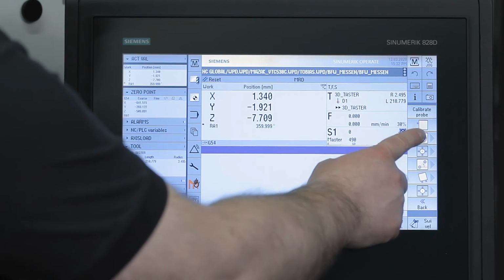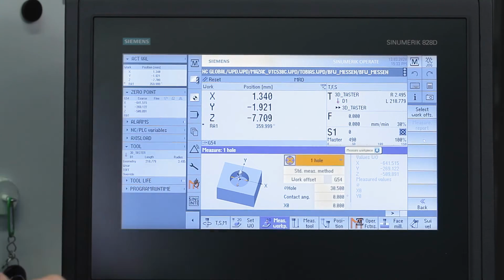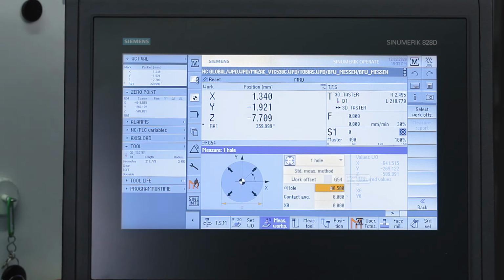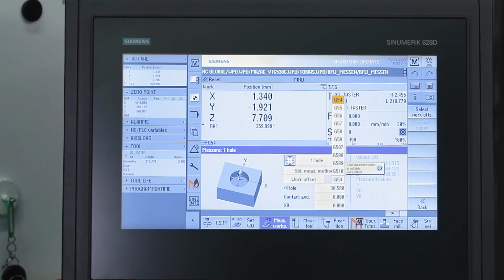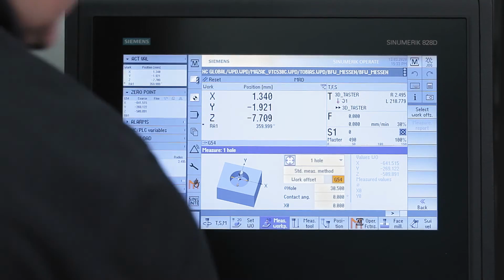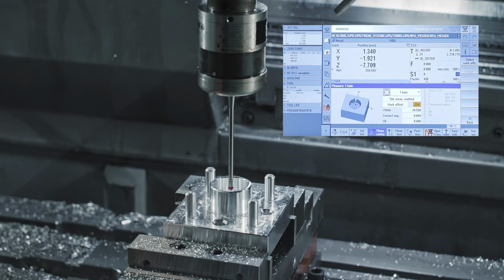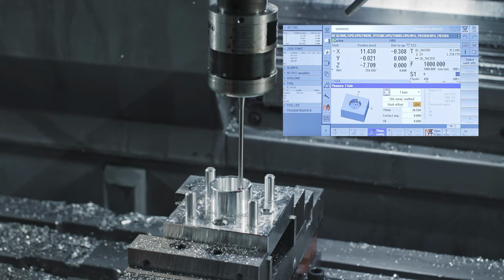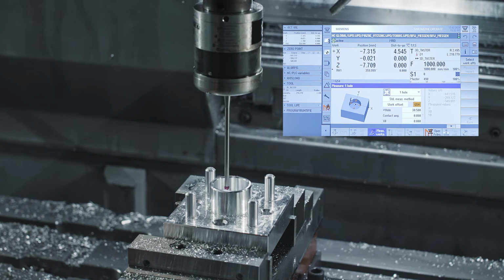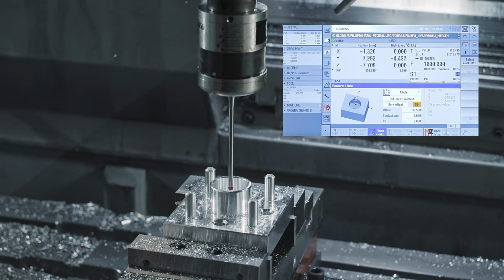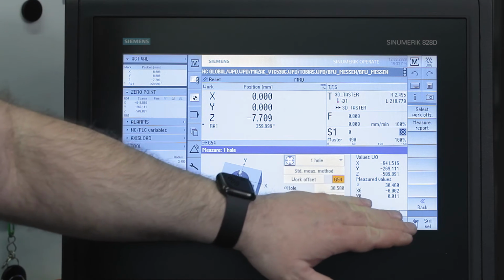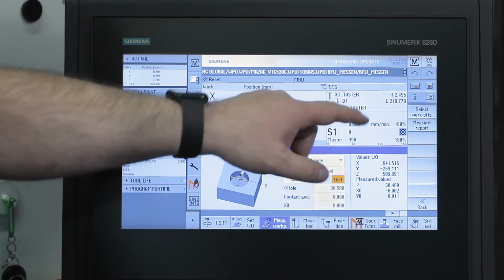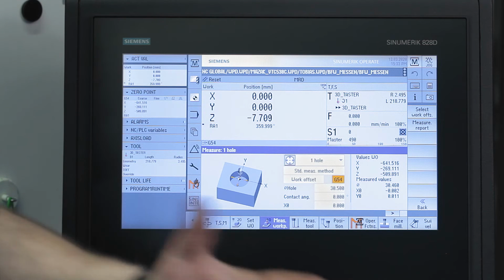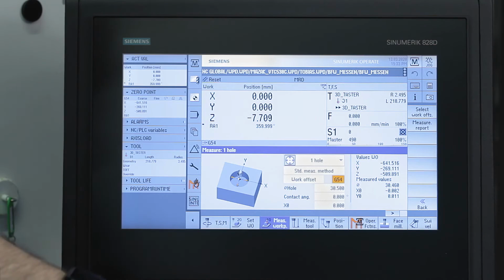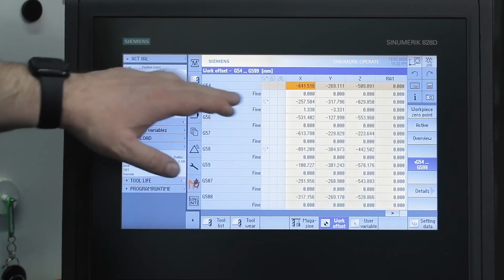Now it's important to set the measuring mode you want to select. In this case, we want to measure a drill hole. Here we set the approximate diameter of the drill hole and the 0 point we want to specify. In this case, it's G54. You also hear the acoustic feedback when the measuring ball touches the sidewalls. That's the measuring procedure, and here is the active G54 work offset and the corresponding parameters of what was measured. Now the 0 point is specified in the offset under G54.